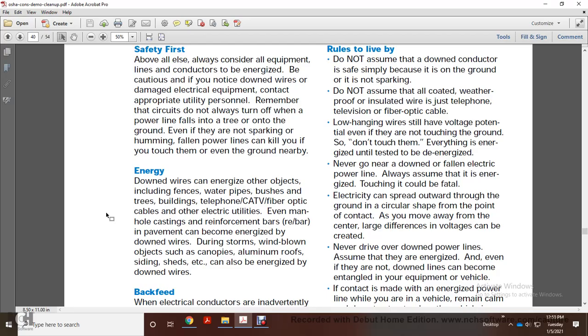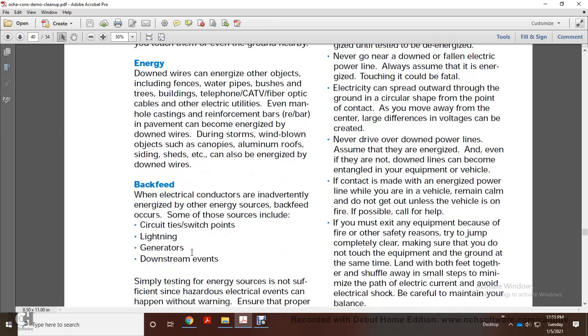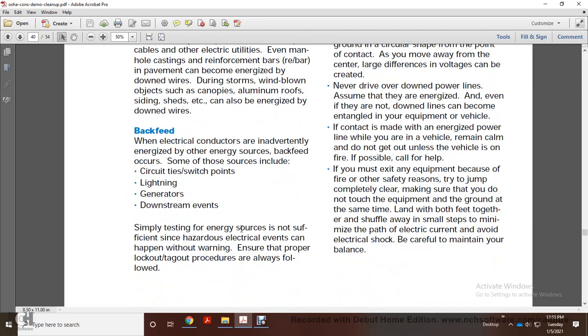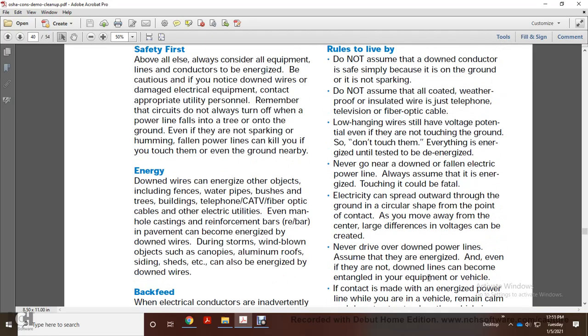Even manhole castings, reinforcement, rebar, and pavement can become energized by down wires. During storms, wind-blown objects, canopies, aluminum roofs, and siding sheds can also be energized by down wires, or by backfeed, where electrical conductors inadvertently come into contact with other energized structures. Energy source backfeed occurs. Some of the sources include circuit ties, switch points, lightning, generators, downstream events. Simply testing the energy source is not sufficient for these electrical hazards. If they happen without warning, ensure the proper lockout tagout procedure is always followed.